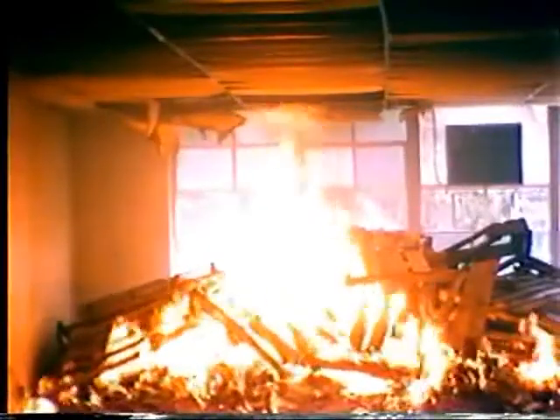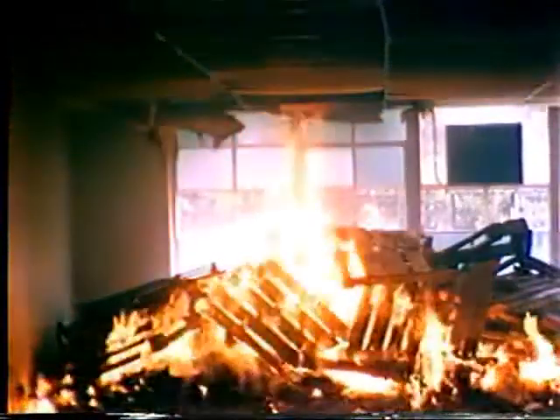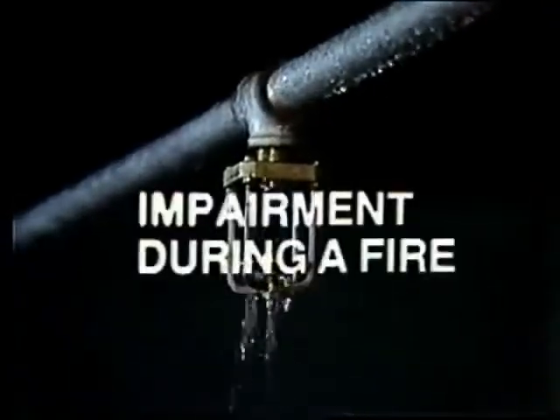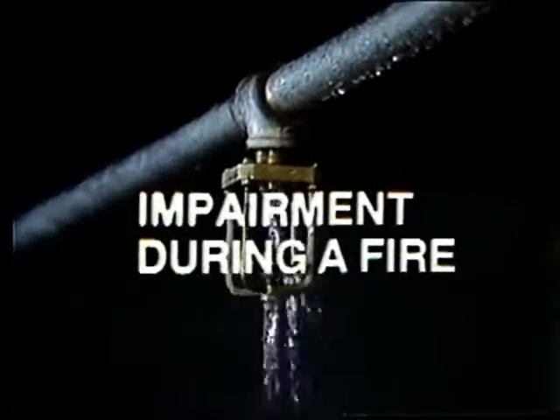In operation, the sprinkler system is an ally to the firefighter. It's on the scene before the fire starts, and in many instances is the difference between a minor incident and an uncontrollable fire. Sometimes sprinkler impairment occurs during a fire because someone closes the valve, stopping water flow to the sprinklers. This premature valve closing is motivated by the following. First, the belief that shutting down sprinklers as soon as possible minimizes water damage. In reality, the water from an adequate sprinkler system is less than that from hose streams to control the same fire. Second, to increase visibility.